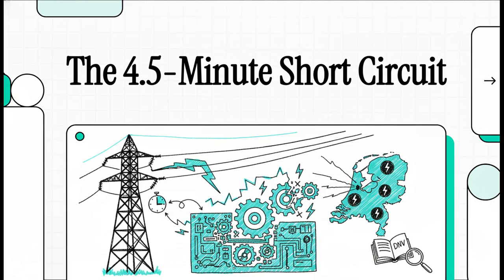On September 2nd, 2022, something happened on the Dutch high-voltage grid that, well, just shouldn't have been possible. A standard short circuit, an event that safety systems are built to shut down in less than a second, was somehow allowed to continue for 4.5 minutes. This caused a massive cascade of failures with some pretty serious consequences. Today, we're going to break down the official DNV report to figure out exactly how this happened.